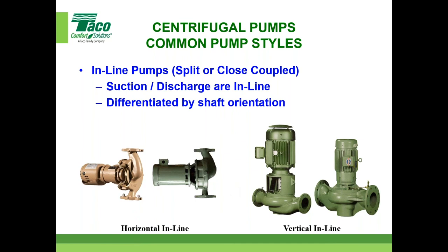I checked quickly on one of your handouts. The IOM manual handout shows the different mounting arrangements for vertical inlines with or without the stand. And actually, the KS models, the split coupled models, you cannot mount horizontally. The direct coupled, the KV models, you can. I wouldn't recommend it, but I have seen them mounted horizontally, meaning the motor is horizontal instead of vertical like you see here, and that's only up to I think 15 horse. Anything above that, it's got to be in this orientation, but that's in the manual as well.